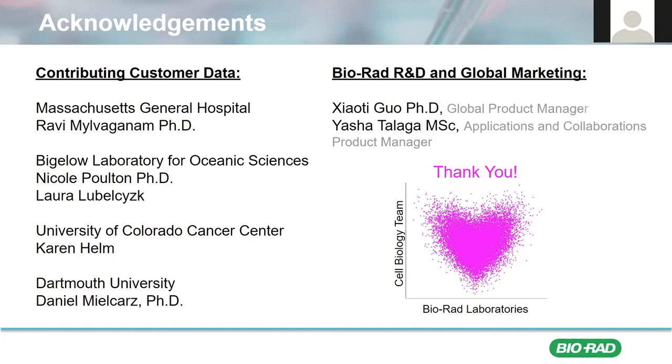And then I saw that you had mentioned about the robotics unit, which was great for people that are doing a lot of high-throughput screening. Have you ever heard of any facilities that have paired the ZE5 with robotic units that automatically carry out the staining — a completely closed-off system where it does the staining and then also does the transfer of the plates and the washes over to the ZE5? Yes, definitely. I think that's a very common utilization. There are really two different options with robotic integration: some turnkey solutions where you have a hotel with your plates and it's loading the ZE5 for you after you've done the upstream cell processing. But there are also several people who have their robotics integrated to a complete workflow from staining to analysis.